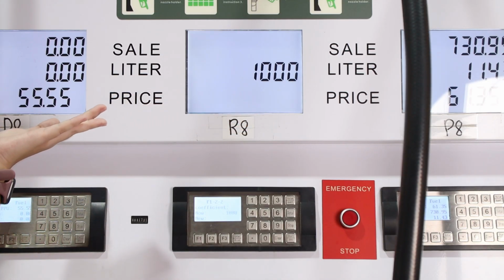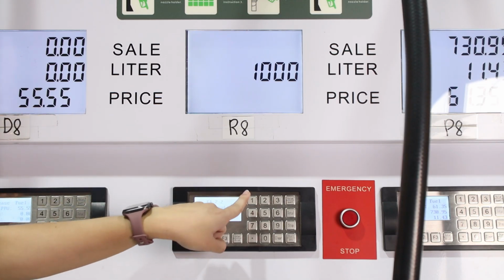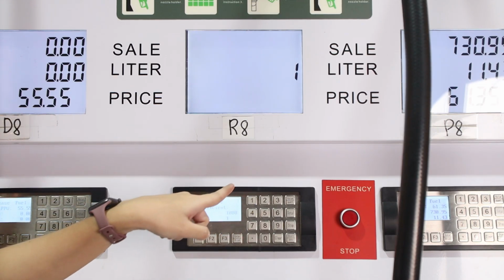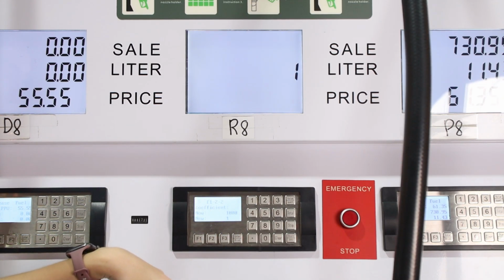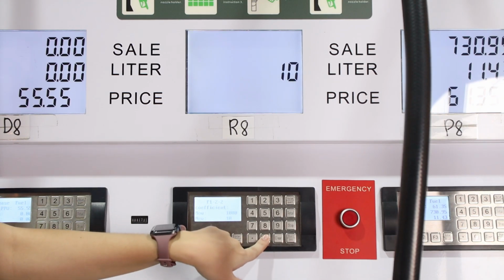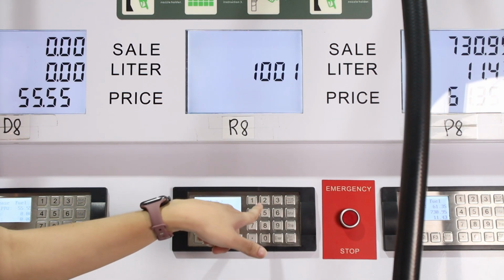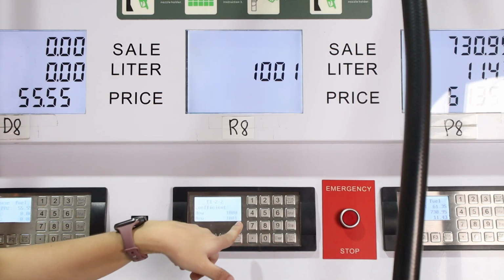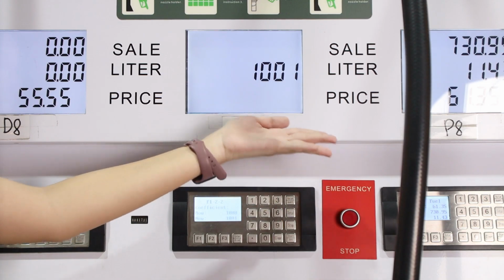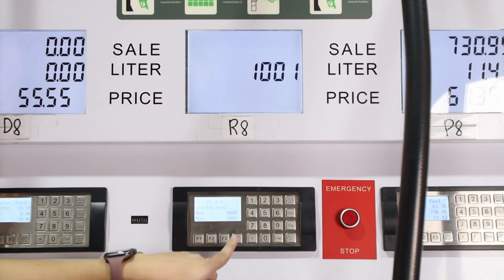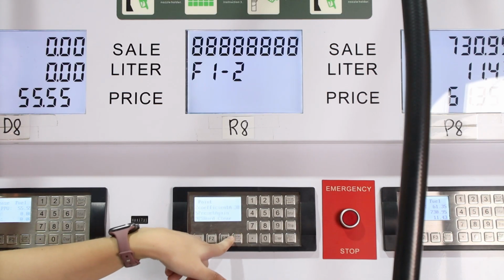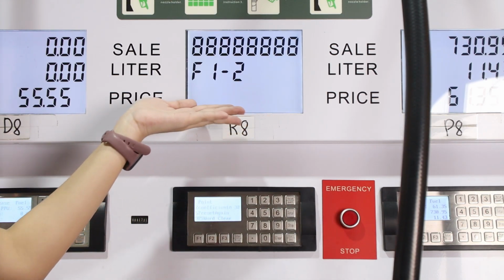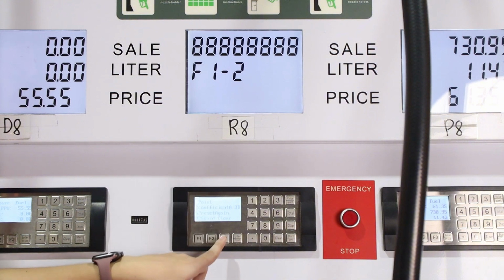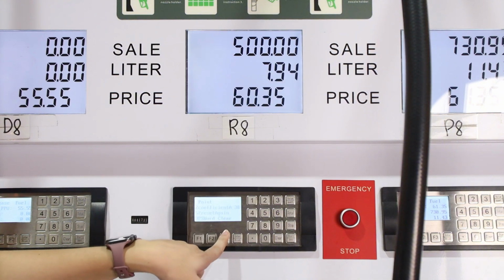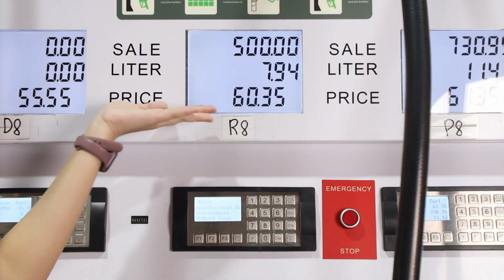1000 is the default. To adjust, increase the calibration: adding 1 is equivalent to 10 milliliters additional. Decrease the calibration: subtracting 1 is equivalent to 10 milliliters less. Input the desired calibration adjustment, e.g. 1001. Press Enter to confirm the adjustment. The display returns to 88888F1-2. Press F3 to exit calibration mode, and the display will show the normal default screen.